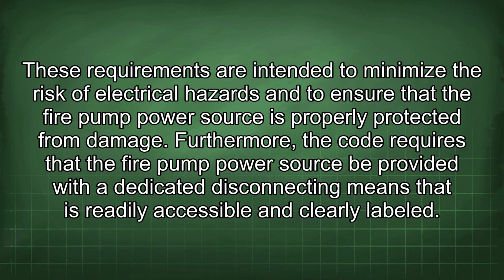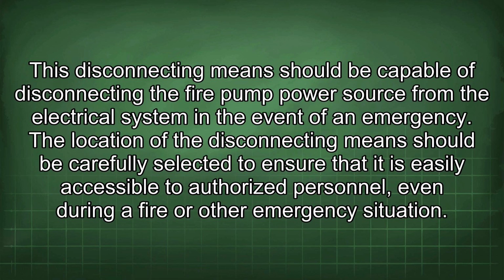Furthermore, the code requires that the fire pump power source be provided with a dedicated disconnecting means that is readily accessible and clearly labeled. This disconnecting means should be capable of disconnecting the fire pump power source from the electrical system in the event of an emergency. The location of the disconnecting means should be carefully selected to ensure that it is easily accessible to authorized personnel, even during a fire or other emergency situation.